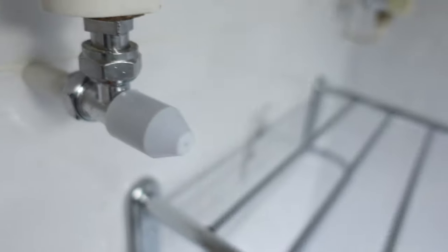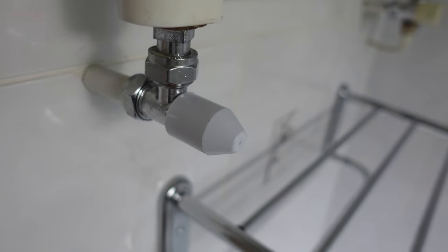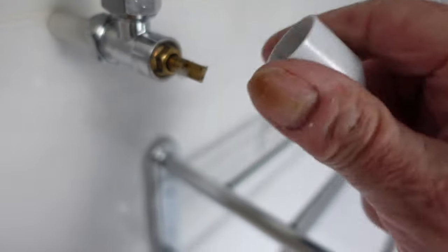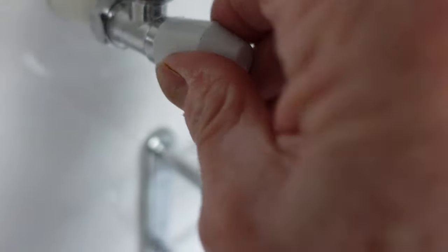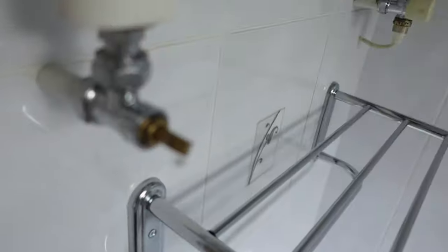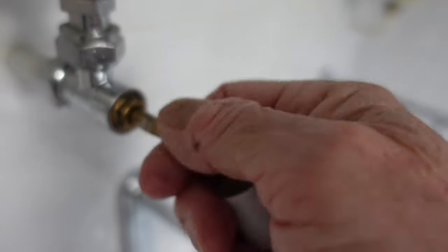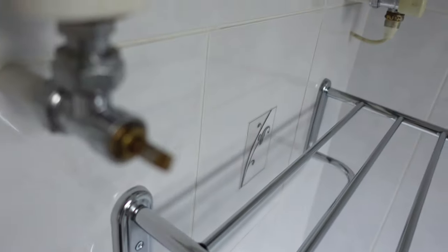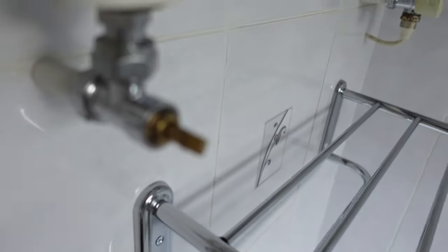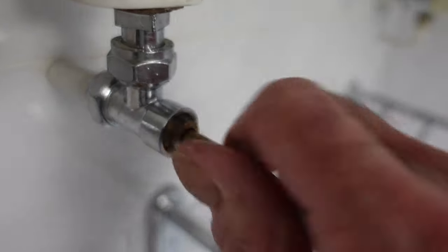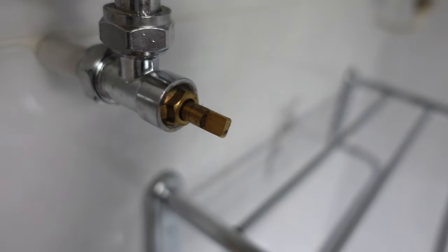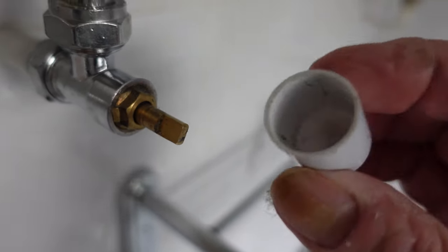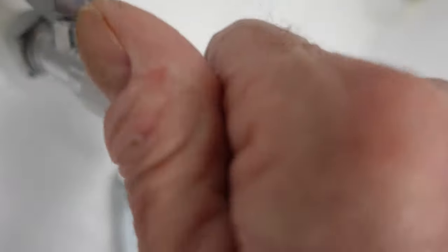She sent a little video and she was turning this one and saying look, it doesn't stop, it just keeps turning. And that's because if I take this off of here, you see there's nothing in there, it's just a cap. Okay, it's just a protective cap. This is what's called a lock shield valve. This one is usually squeezed down a little bit further to a set position, usually to balance the system in the house. Sometimes they'll just be full on, it depends. But whatever, you can say is that this top will just go around and around.